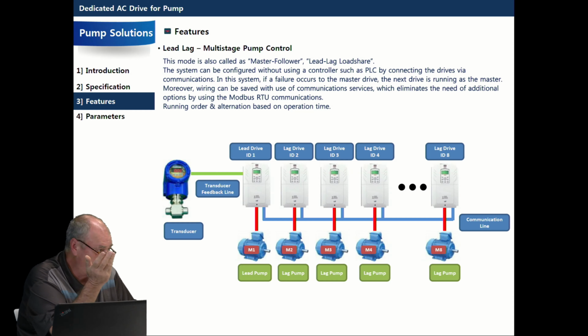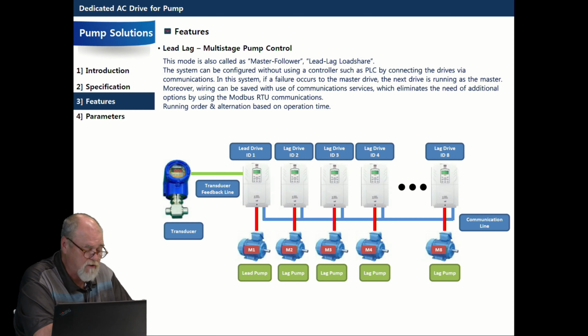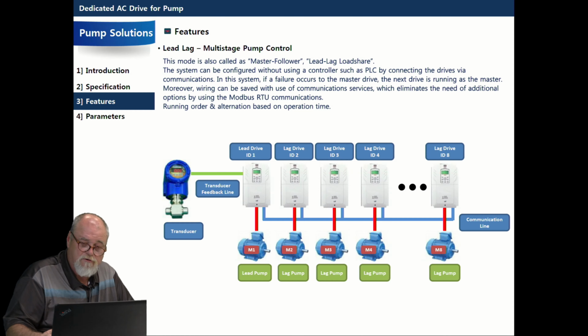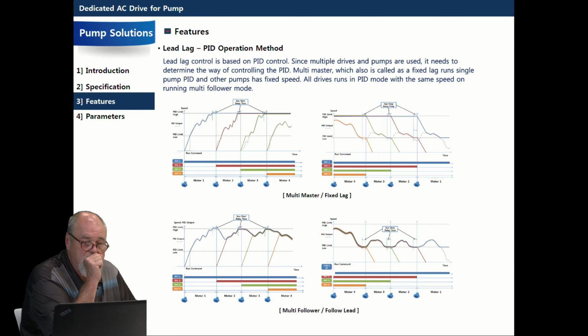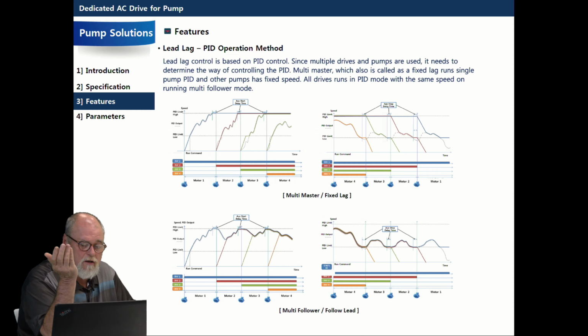When programming this, you can switch automatically between drives based on time or least-run logic. You can have redundant transducers fed back into the system on another VFD in case of a redundant or transducer failure. In lead-lag control, we can do it a couple of different ways: multi-follower on the PID operation, or multi-master where you have a fixed lag.